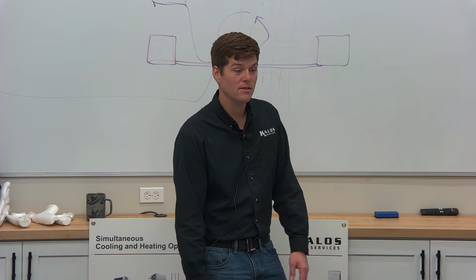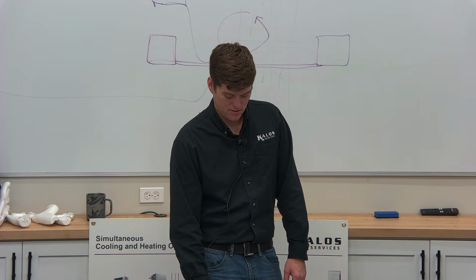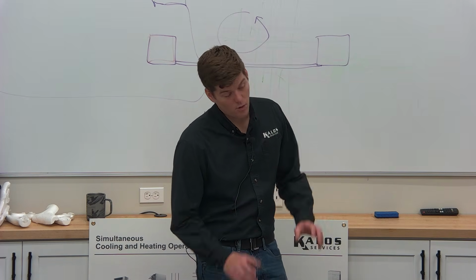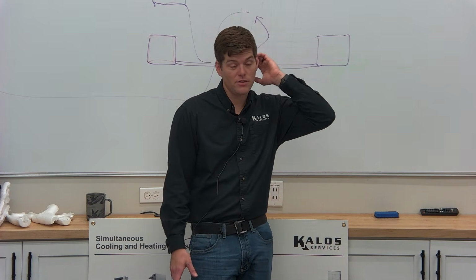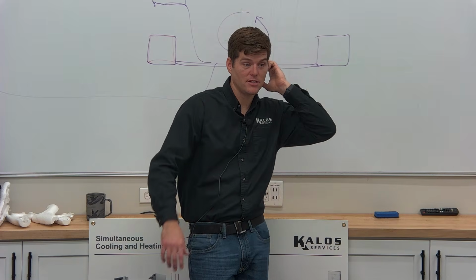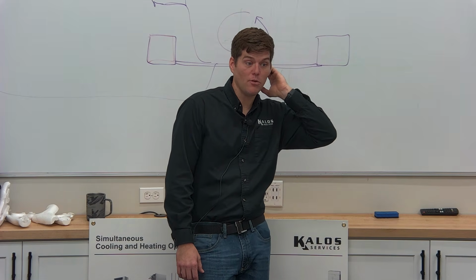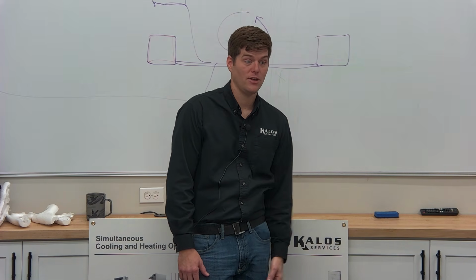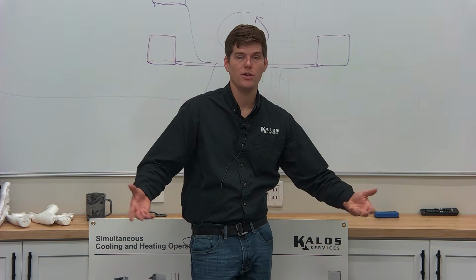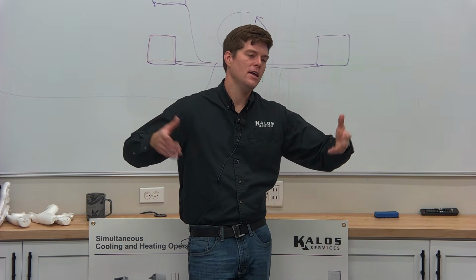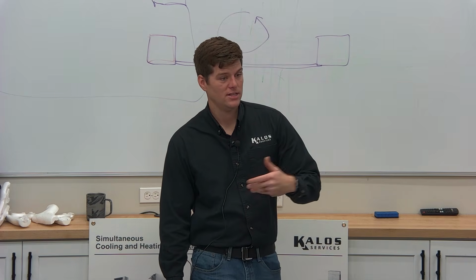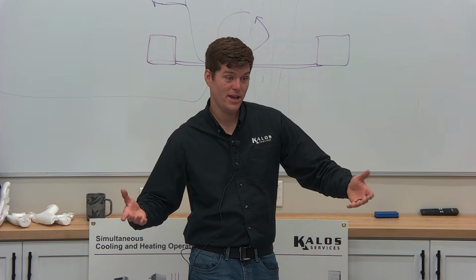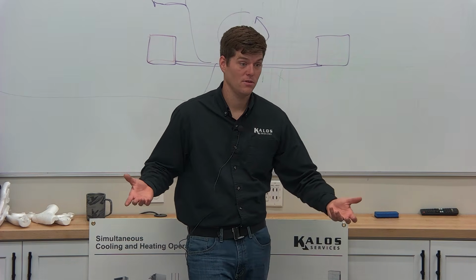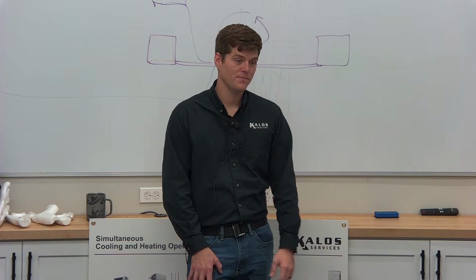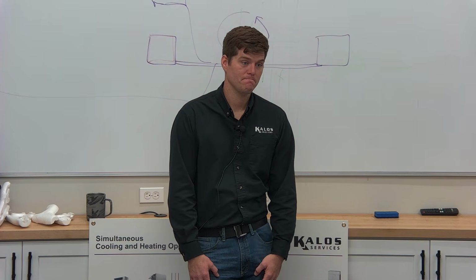The limit, ambient. No, 12 to 18. And that's the wild thing too, the 12 to 18. You're talking about the capacity limitations on the box itself. It's usually actually double what you find on a normal box. So if you get a box with 12 indoor units or, let's say, 18 indoor units and they're all 1 tons, that's 18 tons of cooling capacity. It can actually handle more than that. It can usually handle up to like 24 tons. The limit's really the boxes adding up to the full capacity.